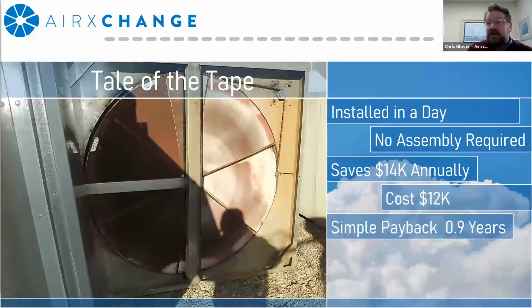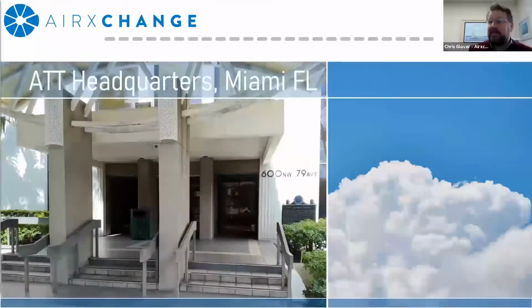The operational savings is about $14,000 annually. Now, this is an area in the country where they have about equal heating and cooling savings. So, some of that's in the summer, some of that's in the winter. The cost of the equipment was $12,000, and the simple payback on the equipment was less than a year for this project. So slide-in cassettes are kind of a fantastic way if you have the ability to maneuver in the space. Really good, cost-effective option. This is the AT&T headquarters in Miami, Florida.